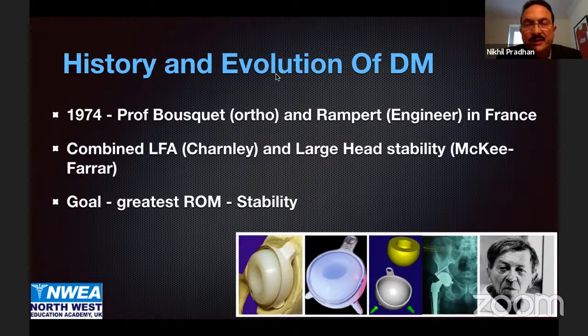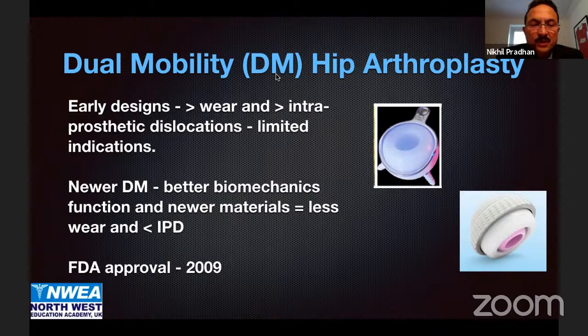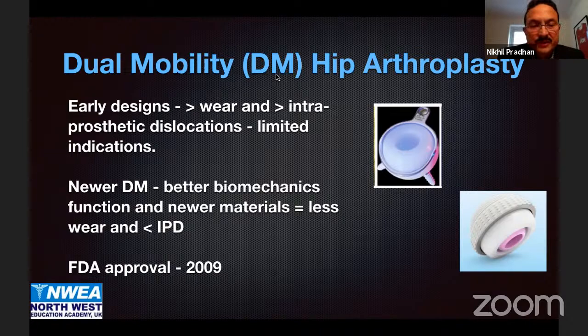The early designs had faults which led to increased wear and intra-prosthetic dislocations, limiting indications and use. With newer dual mobility implants, better biomechanics and newer materials — especially polyethylenes — have reduced the wear rate and the risk of intra-prosthetic dislocation. The FDA gave approval in 2009, which saw increased use in the US, and in mainland Europe, especially France, it's been used in large numbers.